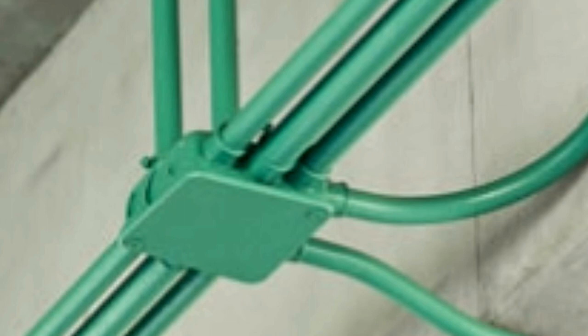Cut the PVC conduit in such a way that it can be attached to the LB fitting and reaches the bottom of the trench. While doing this, enough room should be left for the elbow. Attach the elbow with the adhesive and also attach the PVC into the LB fitting with adhesive.